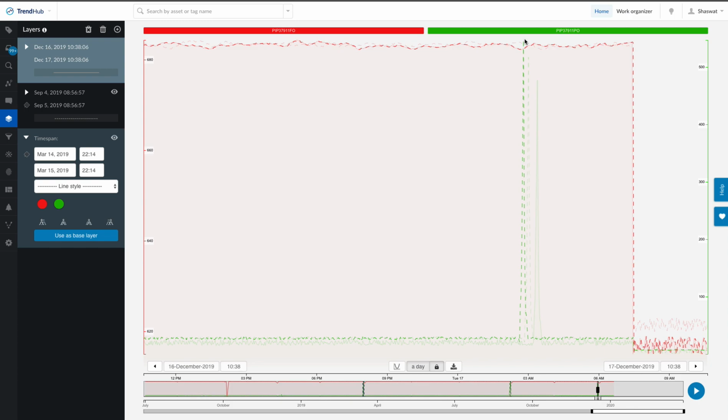And this kind of overpressure scenario can be the result of internal reactions or incorrect operations. They can cause damage to the pipeline internally or can cause damage to the fittings of the pipeline, which results in the leak of crude oil or gas. And exactly this is what happened. Because of these spikes, I guess the metal got damaged, and because of that we saw leaks from different fittings.